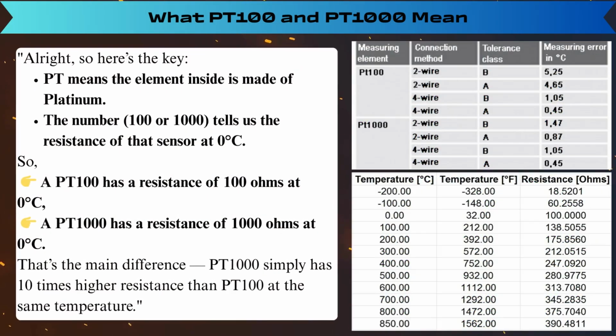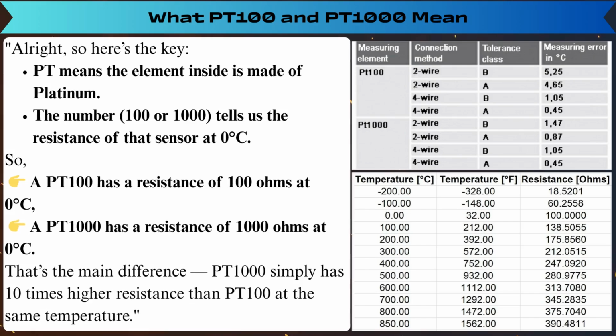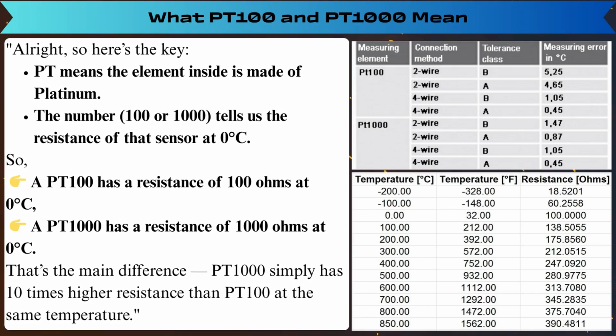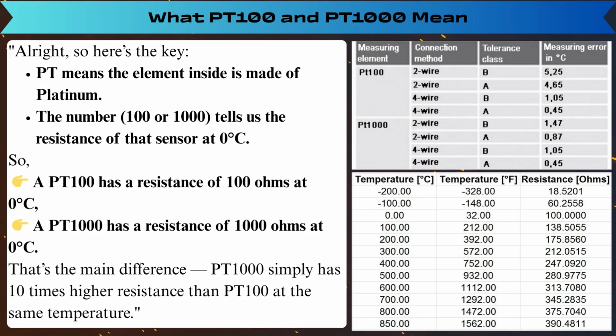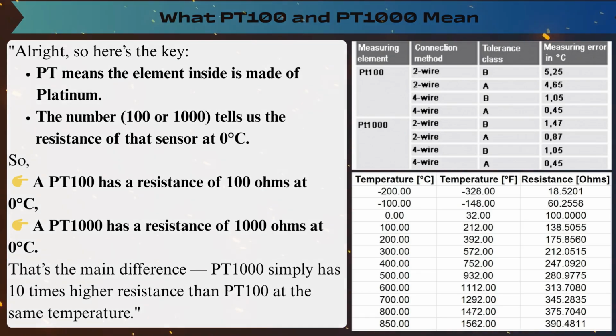What do PT100 and PT1000 mean? Alright, so here's the key. PT means the element inside is made of platinum. The number 100 or 1000 tells us the resistance of that sensor at 0 degrees Celsius. So, a PT100 has a resistance of 100 ohms at 0 degrees Celsius. A PT1000 has a resistance of 1000 ohms at 0 degrees Celsius. That's the main difference. PT1000 simply has 10 times higher resistance than PT100 at the same temperature.